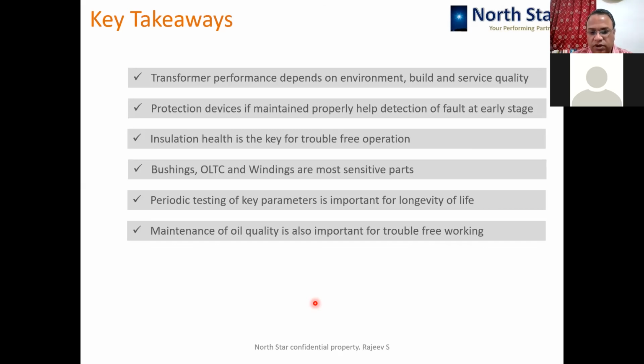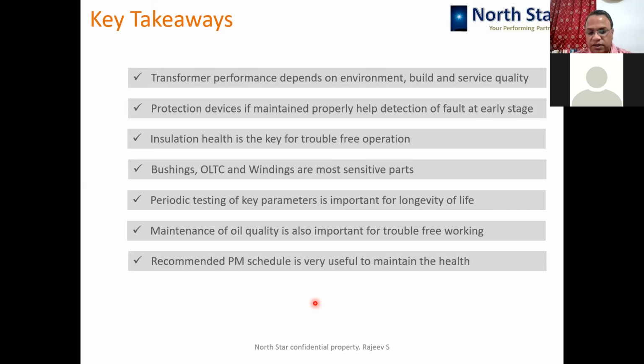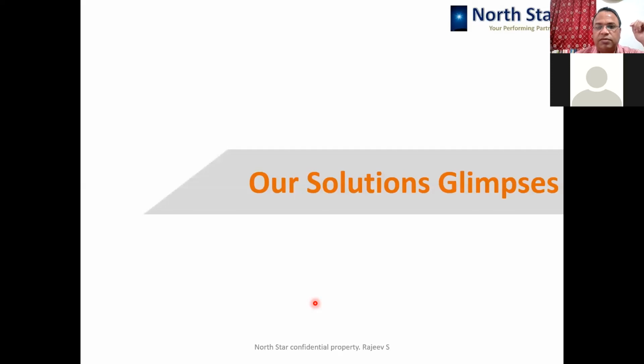Maintenance of oil quality is important for trouble-free working, but excessive filtration, on the contrary, is also not to be done, because that also causes damage to the insulation quality. The recommended PM schedule is for your guidance, and you can moderate it or make it more stringent according to your situation. So this is about today's topic.